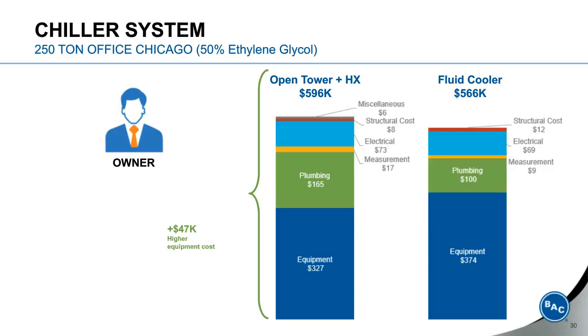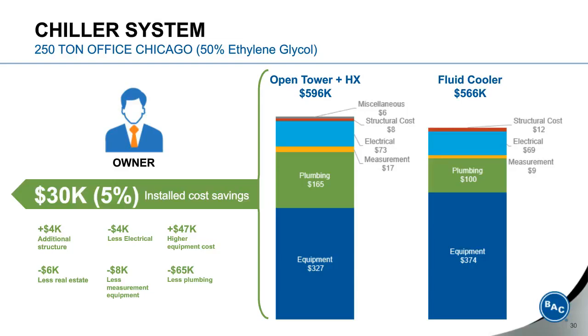So in this study, we wanted to look at what is the impact on the installed cost. When you add all those up, we find that there's $65,000 less plumbing and piping required for the fluid cooler version, $8,000 less in the measuring equipment, the flow meters, pressure gauges, temperature sensors, $4,000 less wiring costs for the fluid cooler system, $6,000 less real estate because we don't take up space in the equipment room. The equipment room can shrink in size. And the additional structure required for the fluid cooler does add back in $4,000. And that's a total installed cost savings for the fluid cooler system of $30,000 in this case, or 5% of the installed cost of the heat rejection system.